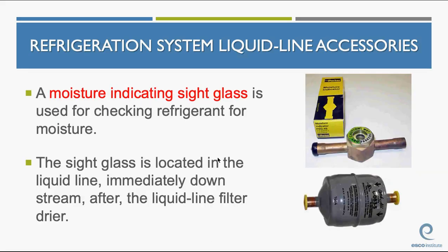A moisture indicating sight glass is used for checking refrigerant for moisture. Does it say any place in here checking refrigerant for a charge? To see if it's charged properly for the sight glass? The sight glass is, yeah, it doesn't. Okay, you cannot use a sight glass to charge a system.